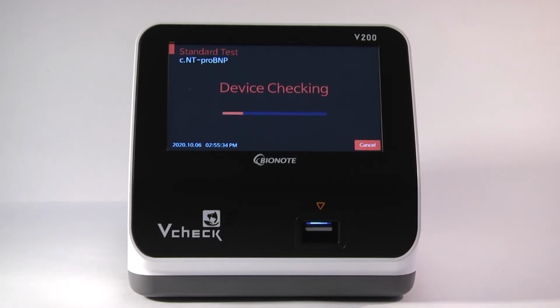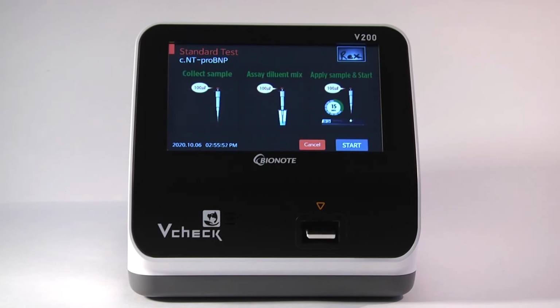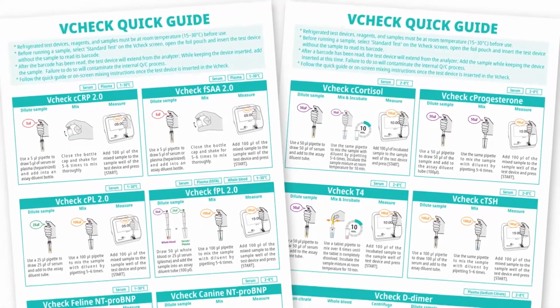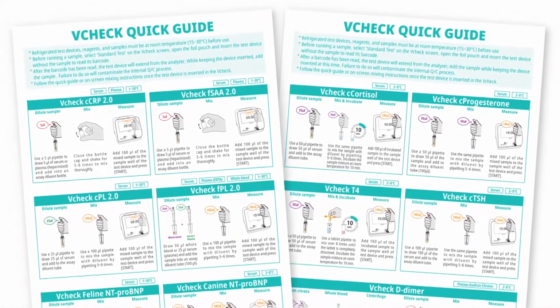Notice that I did not put a sample mix into the device. It is appropriate to put the test device in without having a sample in the device. This is because it will take the Vcheck a few seconds to recognize what test you are running. It takes all the information off of the 2D barcode, and once it knows what you're running, it will display the instructions on the screen. Follow the laminated quick guide that comes with the Vcheck regarding how to prep the sample for all 11 tests.